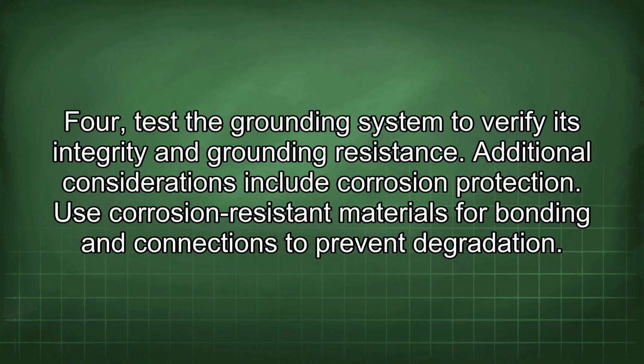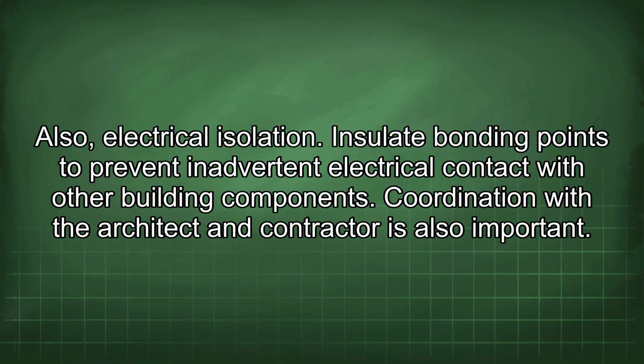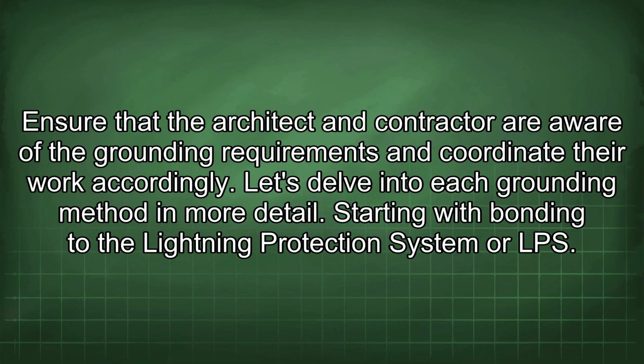Additional considerations include corrosion protection. Use corrosion-resistant materials for bonding and connections to prevent degradation. Also, electrical isolation. Insulate bonding points to prevent inadvertent electrical contact with other building components. Coordination with the architect and contractor is also important. Ensure that the architect and contractor are aware of the grounding requirements and coordinate their work accordingly.